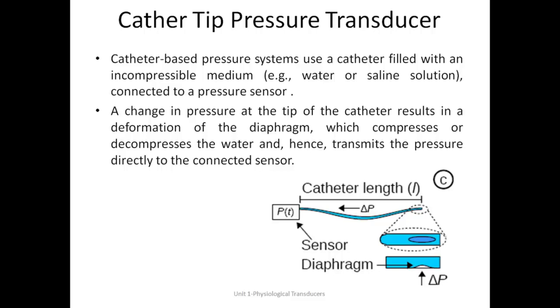From one end, if the pressure is exerted inwards, the diaphragm is moved inwards inside the catheter, and the pressure gets transmitted through this incompressible medium to the other end. The other end of the catheter bulges out and exerts the same pressure on the sensor, the piezoelectric sensor or the capacitive sensor that is placed on the other end. Okay, so whatever pressure you have exerted on the diaphragm, the incompressible medium will exert the same pressure to the other end of the catheter tube, and that pressure will be transferred to the piezoelectric crystal attached over here, and that piezoelectric crystal will take that pressure and generate a voltage signal.